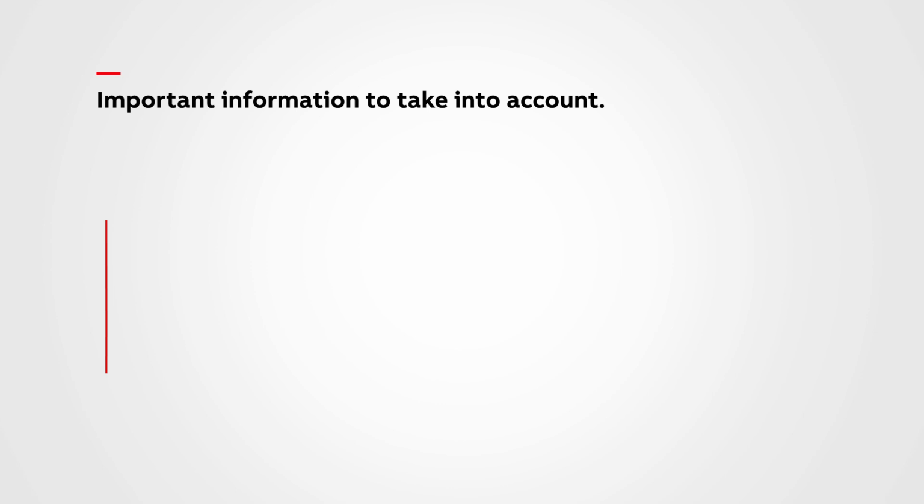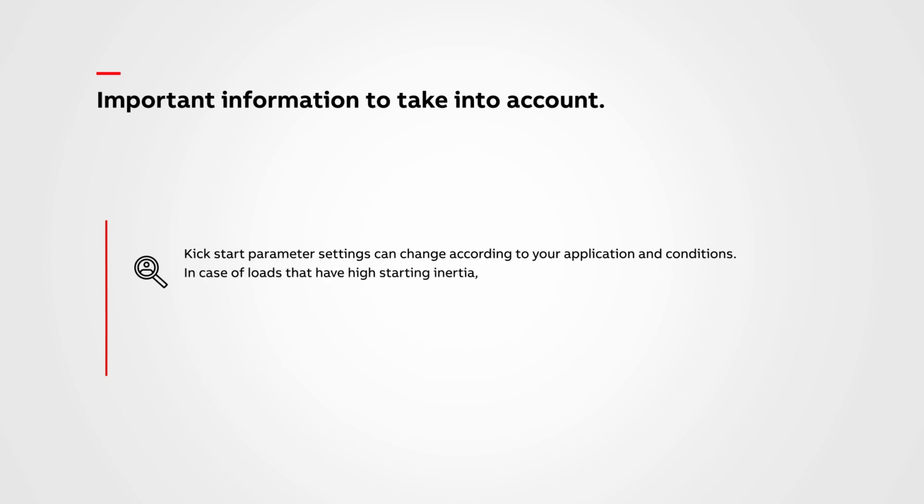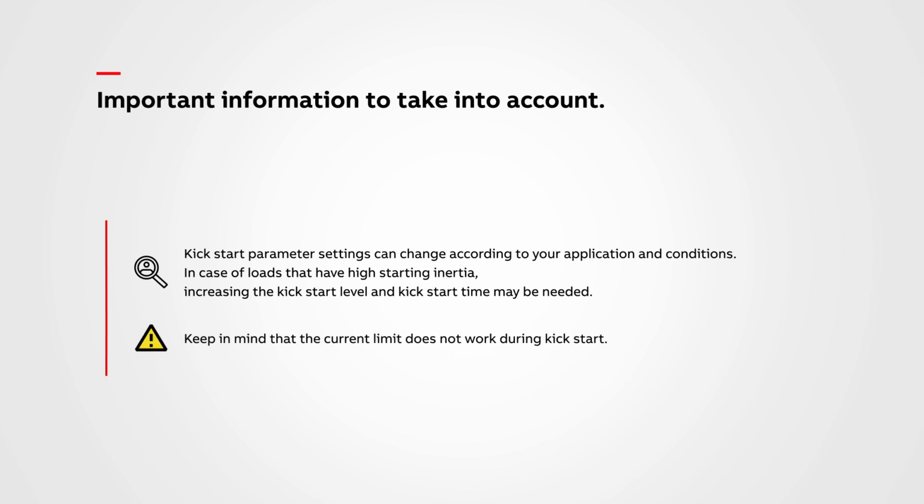Important information to take into account. Kickstart parameter settings can change according to your application and conditions. In case of loads that have high starting inertia, increasing the kickstart level and kickstart time may be needed. Keep in mind that the current limit does not work during kickstart.